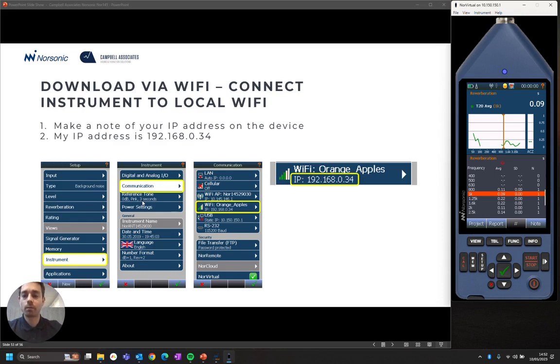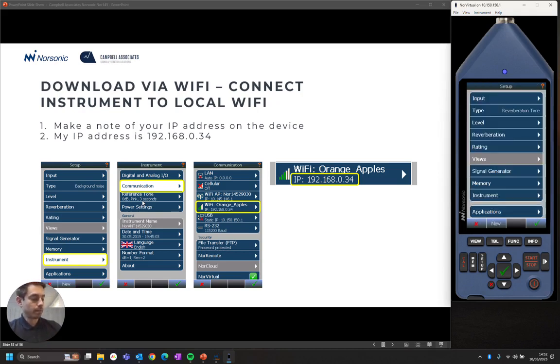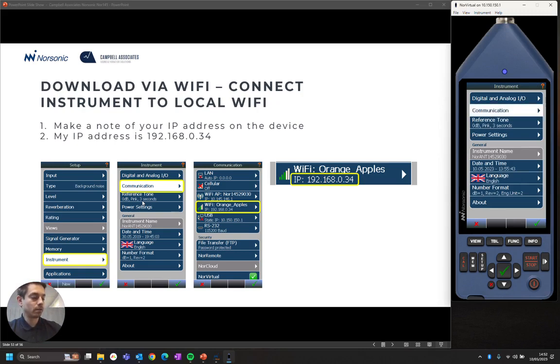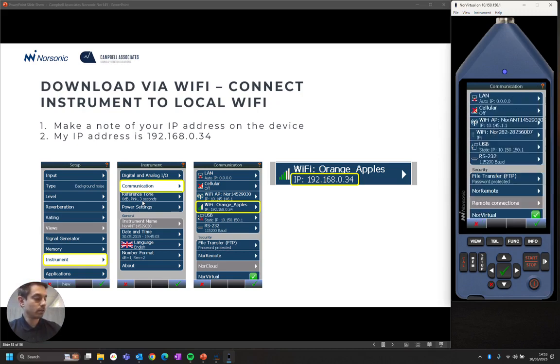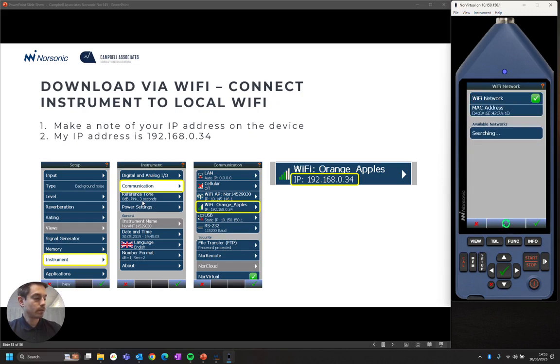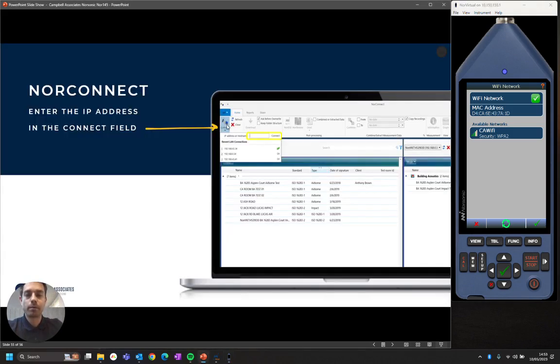If you're looking at using the Wi-Fi method, this can be done by making sure that your meter connects to the Wi-Fi in the local network. If you go to Setup, Instruments, Communication, then go to Wi-Fi, then you'll be able to search for the network, type in the password, then you'll be given an IP address. In my case, it's 192.168.0.34. I then would type this into the software. So in the software, you use the connect button, you type in the IP address, you press connect, and then the measurements will appear on the right-hand side.